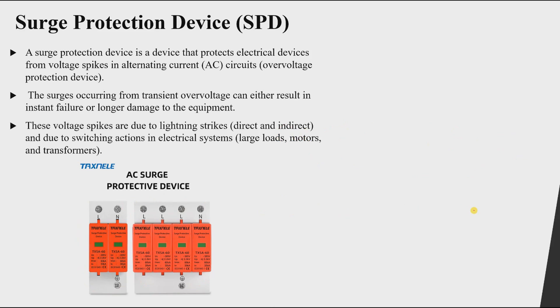Voltage spikes occur due to two main reasons: number one, lightning strikes coming from the sky — which can be direct or indirect — and number two, switching actions in the electrical system. When we switch large loads, motors, or transformers on and off, it can lead to large transient overvoltages.